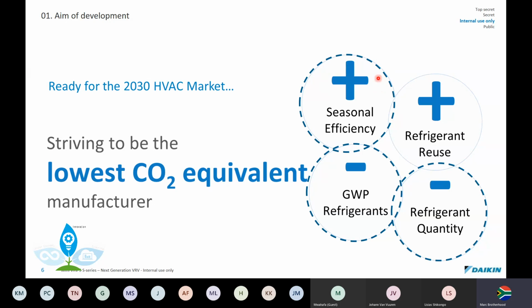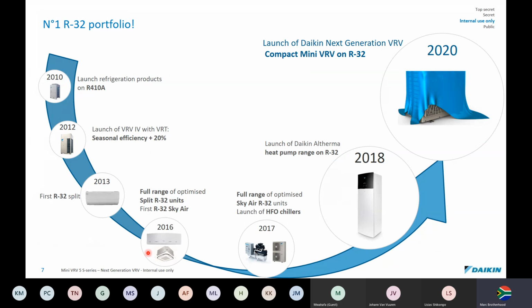So the advantages of this will be seasonal efficiency, lower global warming potential of refrigerants, and also there will be less refrigerant in the units because of the energy content, the enthalpy, and specific heat capacity of R32. So we do not have as much refrigerant in a mini VRV using R32 compared to R410A. If we look at the portfolio on how the R32 came about: in 2010, the launch of refrigeration products on 410A. In 2012, the launch of the VRV4 with variable refrigerant temperature, which when activated could have a seasonal efficiency of 20% over and above the current efficiencies.